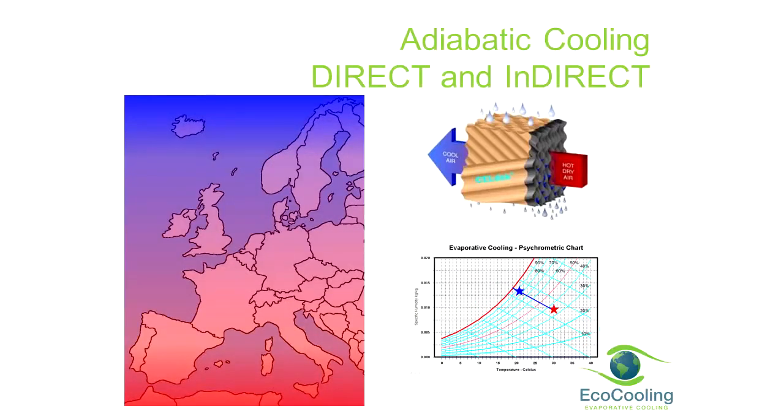Firstly, if you're trying to cool a data centre, it's cold outside most of the time. This is not a difficult concept. But also, outside on hot days, it's also low relative humidity, and there's a thing called the wet bulb temperature of the air, which, if you put water in contact with air, it will cool down. And there is actually a way of using that in a variety of ways to cool your data centre and save capital costs, save OPEX, and also make life a little bit simpler.